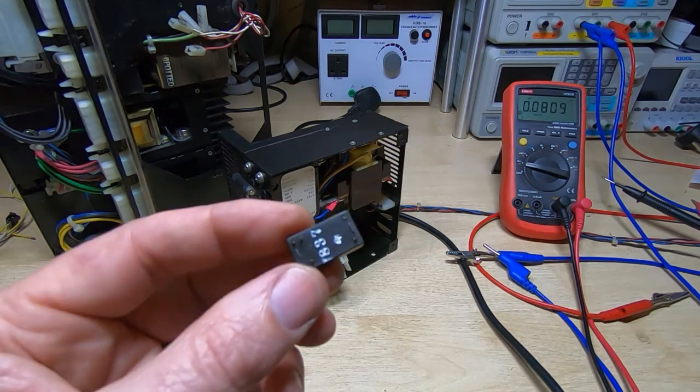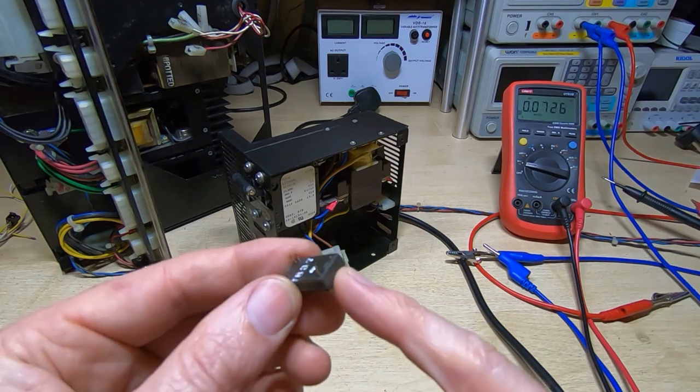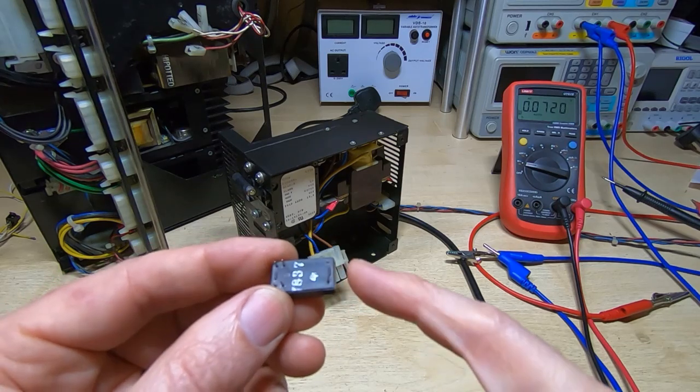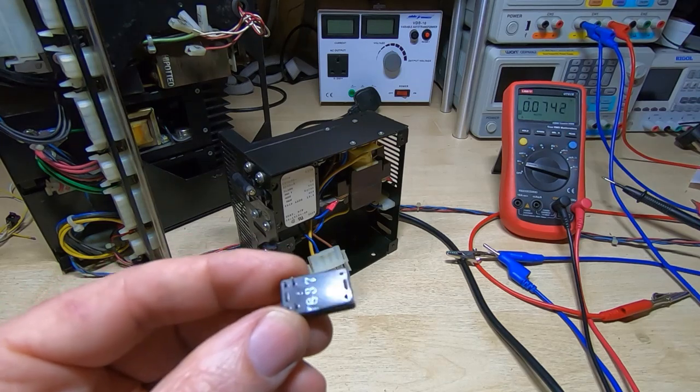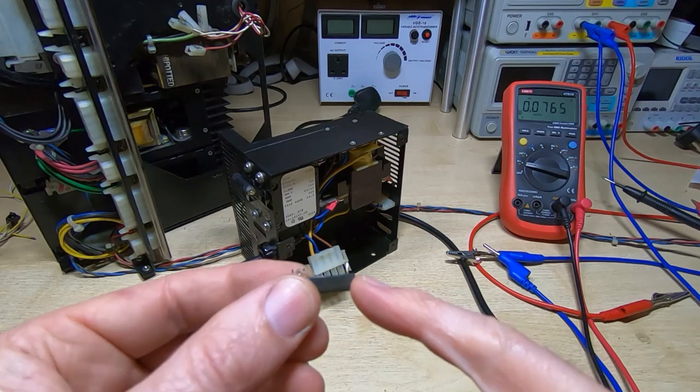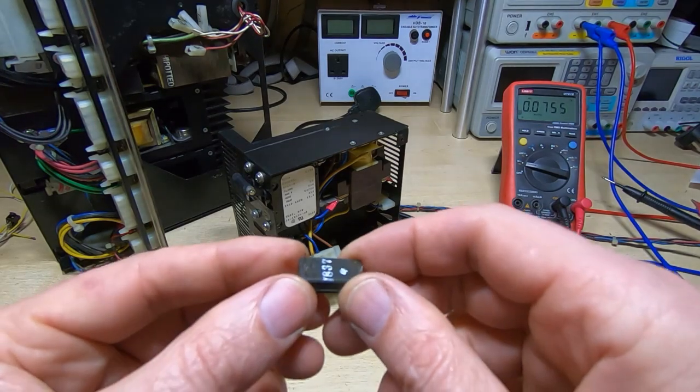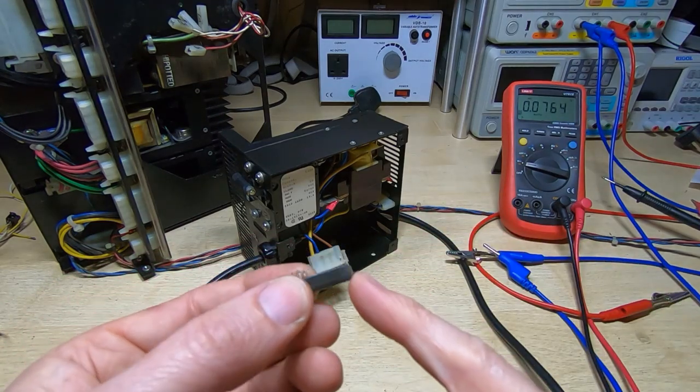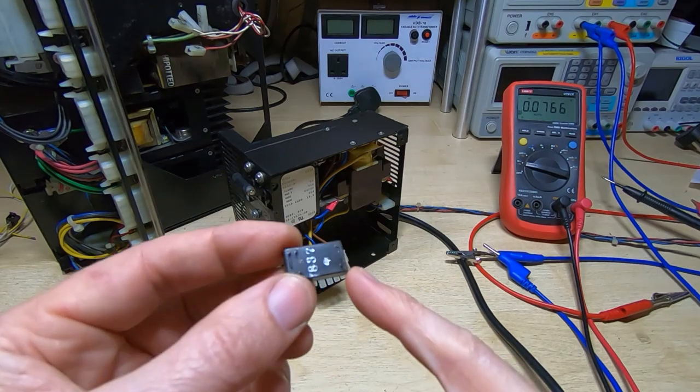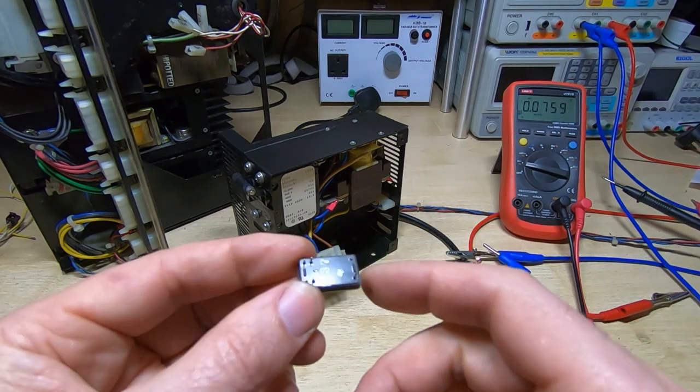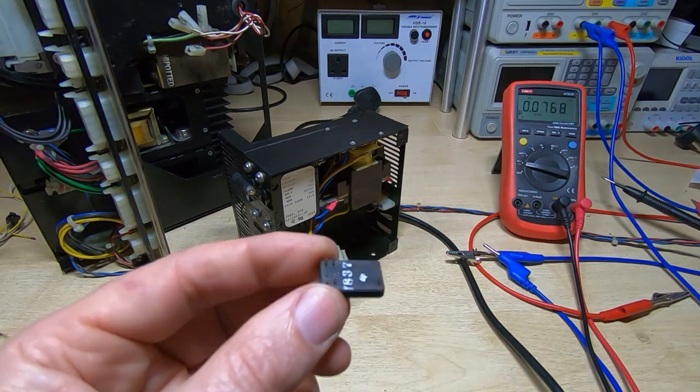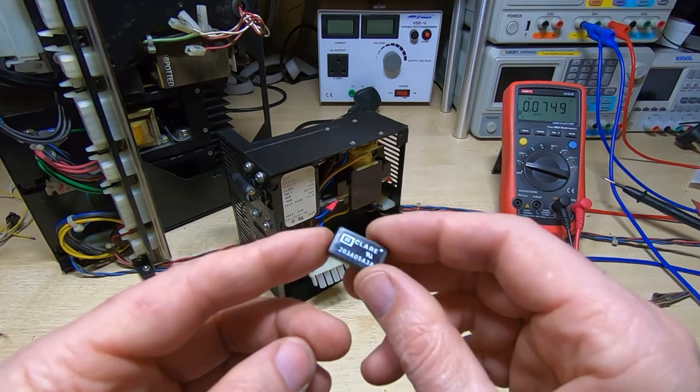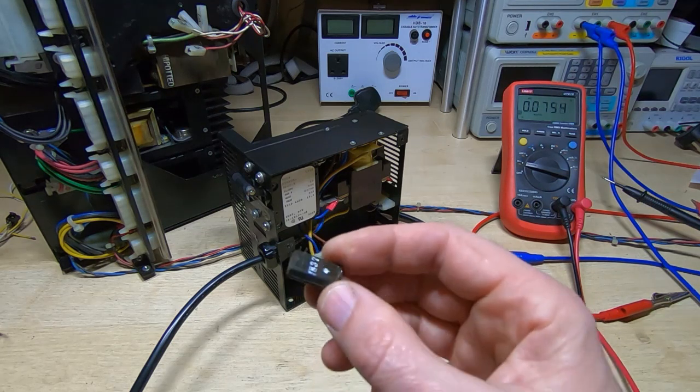OK, well, unfortunately the pin has broken off flush with the case of the device, so I can't really solder anything onto it. I could, of course, remove material from around the pin and attempt to do it that way. But I'm going to have a look for a replacement first. The only reason I'm not that keen on doing that is looking at the rest of the pins. They're also looking fairly badly corroded, so I don't think it's going to be long before they snap off. It's a fairly simple device. It's just an opto isolated triac. It's just there to allow a degree of isolation between the remote control inputs and the mains-driven contactor. So I'll look for one of these, see if I can find a suitable replacement and move on with the repair. But I thought that was quite interesting.